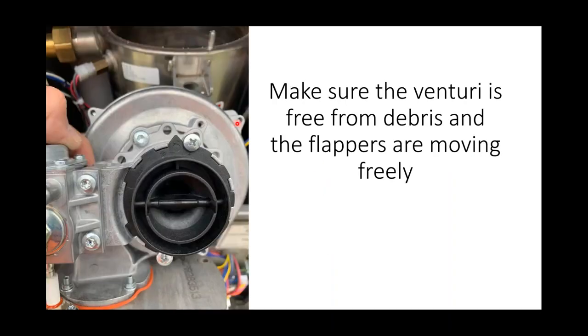So while we have it all apart, we also want to check the venturi, the air venturi. It's going to have some flappers in there. We want to make sure that the flappers are moving freely, that there's no debris in there, like pollen buildup or leaves or bugs or anything that may have found its way inside of the cabinet. We want to make sure that this is free from any of the debris, which could cause some issues further on down the line.